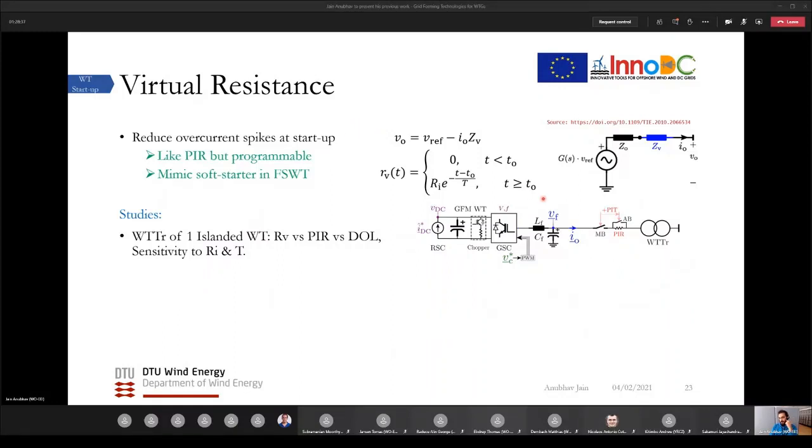its benefit in the scope of a single islanded wind turbine energizing its transformer. We compared a direct online energization versus having a real actual PIR, or versus having this virtual impedance programmed into the grid forming control of the grid side converter.